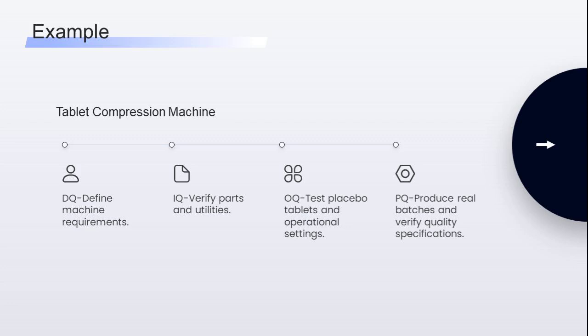Let's take an example with a tablet compression machine. During DQ, you define that you need a machine with 16 stations, 10,000 tablets per hour, and 10–30 kN compression force. During IQ, verify all parts installed per manual and utilities connected. During OQ, run placebo tablets and test speed and weight variation. During PQ, produce real batches and check hardness, disintegration, weight, and thickness — everything meets specs.